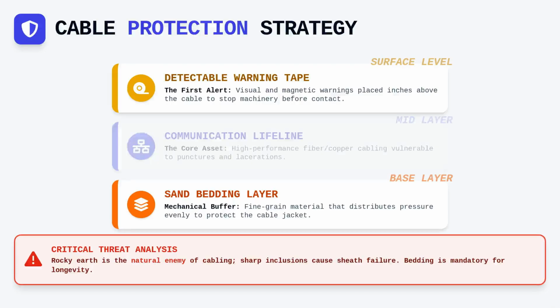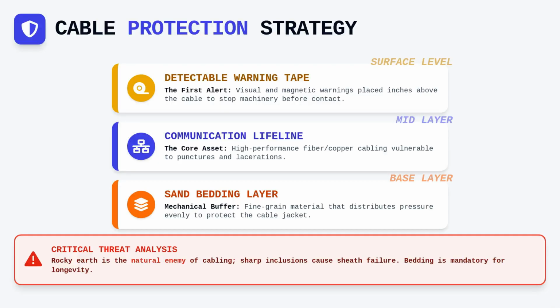Above this layer, the installation of detectable warning tape serves as a vital last line of defense, providing a clear visual and magnetic warning to future excavators. This tape should ideally be placed several inches above the cable to ensure it is intercepted well before any heavy machinery makes contact with the actual communication lifeline.